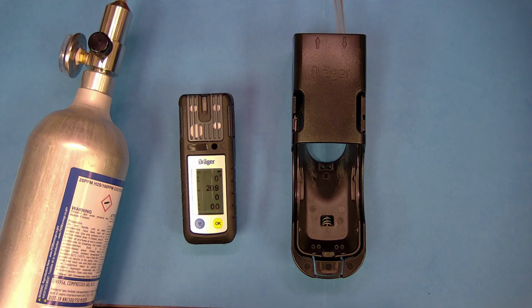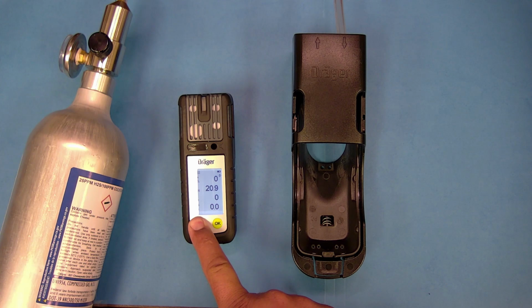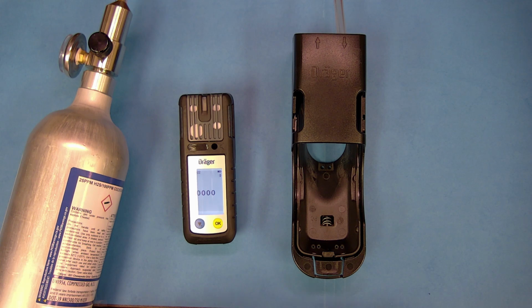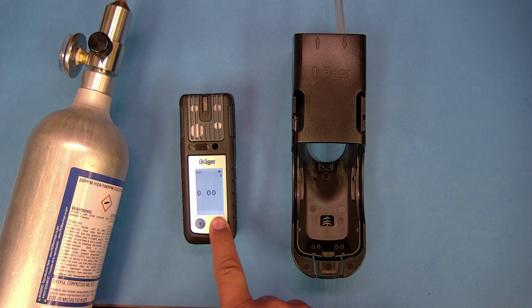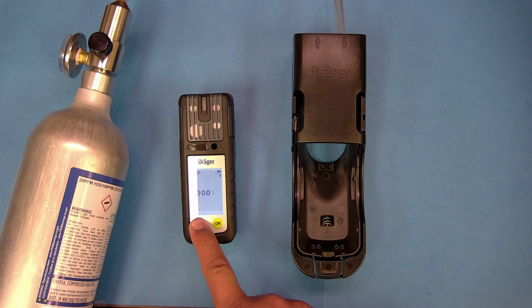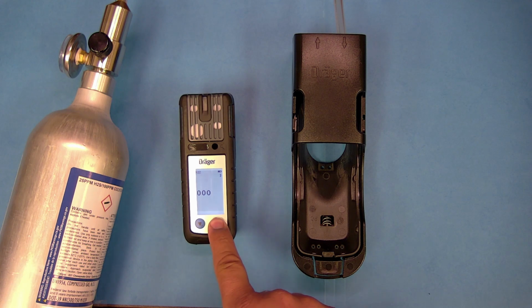To calibrate your monitor manually, you must enter your monitor into the calibration mode through the standard menu. To do this, hold down on the blue button until you see 4 zeros on your screen. Typically, the password will be 0001 unless changed by your company safety professional. You'll see the first 0 is flashing. Press the green button 3 times to get to the 4th and final 0 on your monitor screen. Once the 4th 0 is flashing, you'll press the blue button once to increase it to the number 1, and from there you can press the green button one last time to enter the menu.